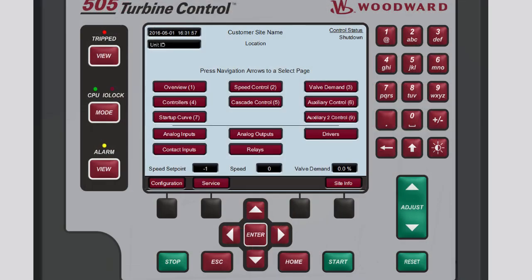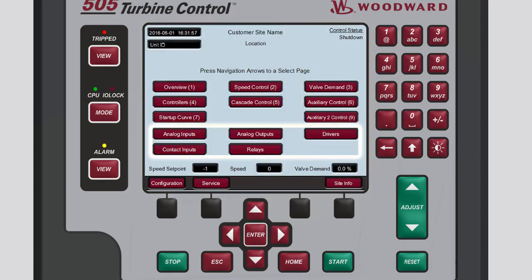Once configured, the 505 boots up to the home screen. The buttons displayed on this main screen vary depending on the functionality you configured for your particular 505. The buttons on the home screen are divided into two categories: Run Operation and Input Output. The Run Operation buttons are located on the top half of the screen and allow you to access screens pertaining to running and operating the turbine. For example, the Overview screen shows a summary of configured controllers. The Input Output buttons are located on the bottom half of the screen and allow you to access screens that display the status for all available channels for the different types of inputs and outputs.